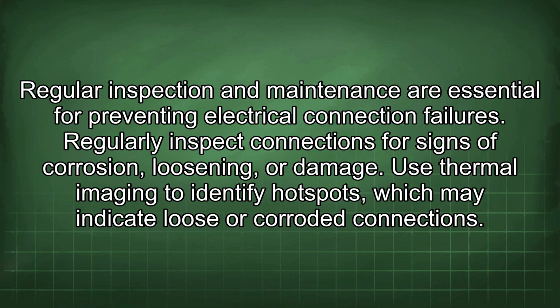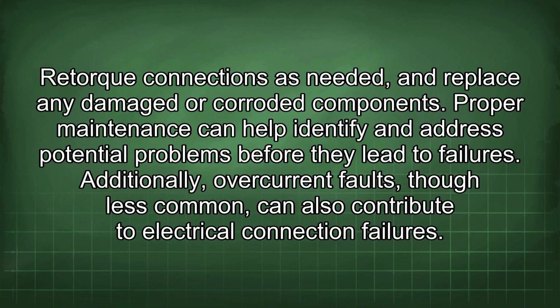Regular inspection and maintenance are essential for preventing electrical connection failures. Regularly inspect connections for signs of corrosion, loosening, or damage. Use thermal imaging to identify hotspots, which may indicate loose or corroded connections. Retorque connections as needed, and replace any damaged or corroded components. Proper maintenance can help identify and address potential problems before they lead to failures.